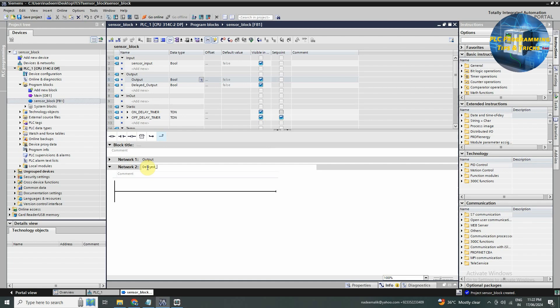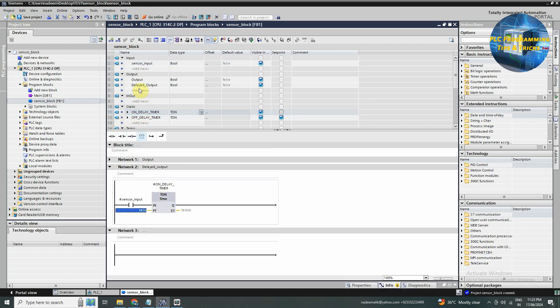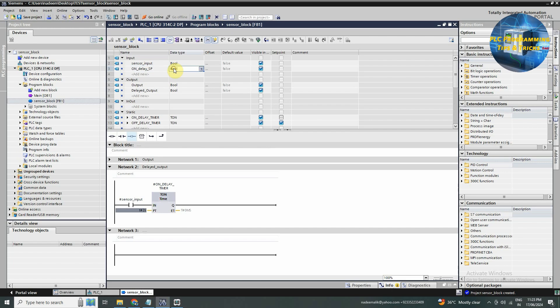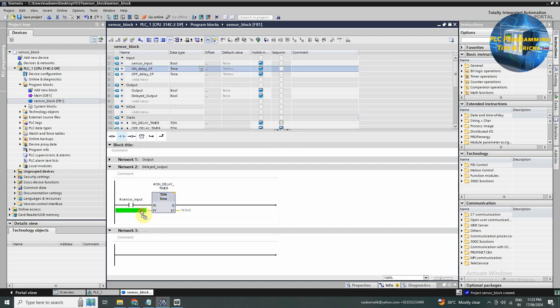In network number two, we will write a logic for the delayed output. We will drag and drop a normal open contact and assign the sensor input tag. Next we will drag and drop a TON timer and assign the on delay timer tag to it. Next we will create two timer setpoint tags named as on delay setpoint and off delay setpoint with time as data type. Now we will drag and drop on delay setpoint to the PT input of the TON timer.